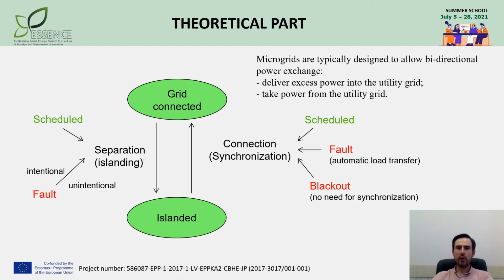Well, as regarding island operation, during island operations the microgrid system is not connected to the grid and the load is powered by distributed energy resources only. The islanded mode can be normal if the islanded microgrid is able to self-balance and doesn't require an external source. Such mode can be preferable to avoid bidirectional power flows and allow using simplified protection schemes.